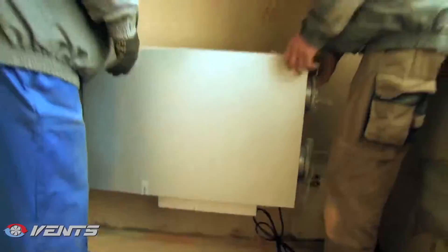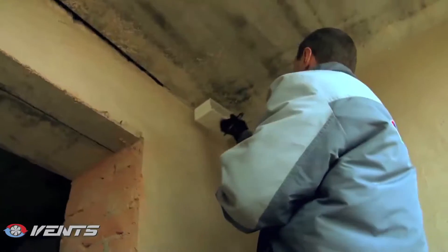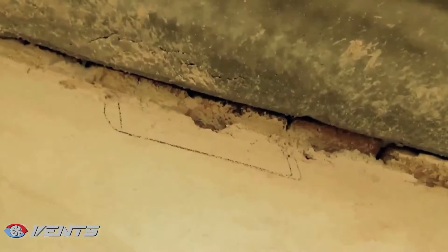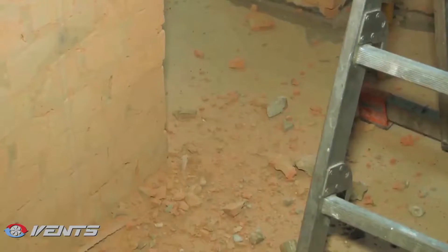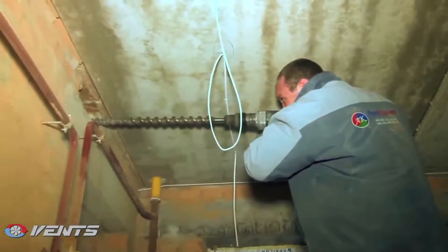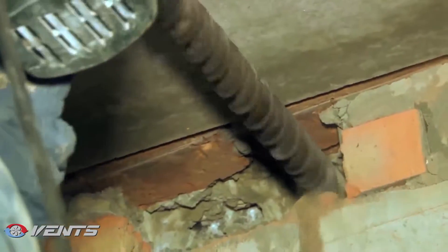This flat has a balcony, which fits the bill. Since the balcony windows reach the ceiling, the air handling unit is installed on the end wall of the balcony, and later hidden in a cabinet mounted below the windowsill level. The only element of the ventilation system requiring periodic inspection is the air handling unit, which necessitates proper access to all of its parts for convenient maintenance and repair. The air ducts are similarly mounted onto the inner wall of the balcony, to be covered with gypsum boards with a 120 mm offset.